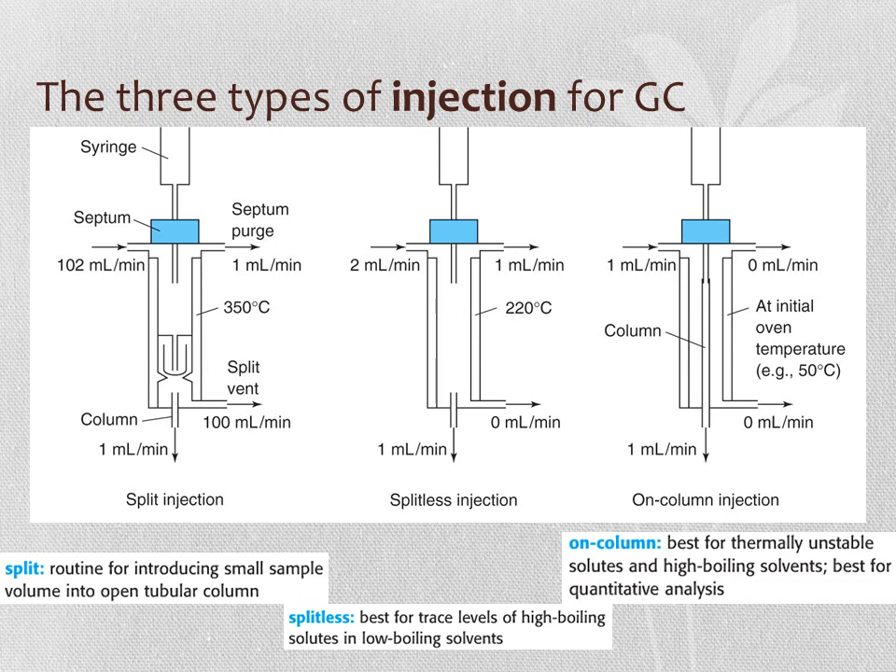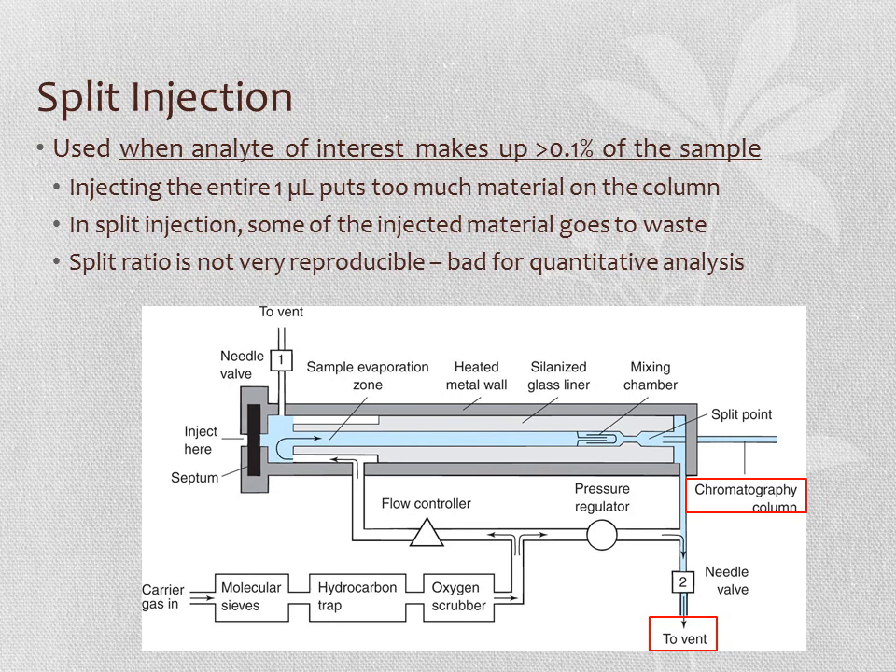There is also a 1 mL per minute septum purge, sweeping away any gases leaking through the septum. Splitless injection uses a similar setup but has no side-sweeping gas—about 1 mL per minute sweeps the injection port and 1 mL per minute goes to the column. On-column injection sends all gas straight onto the column. Split injection is used when the sample is fairly concentrated—in GC, this can mean more than 0.1% of the sample. Injecting a full microliter of a concentrated sample would overload the column, so the excess is sent to waste. However, the split ratio is not very reproducible, which can be problematic for quantitative analysis.